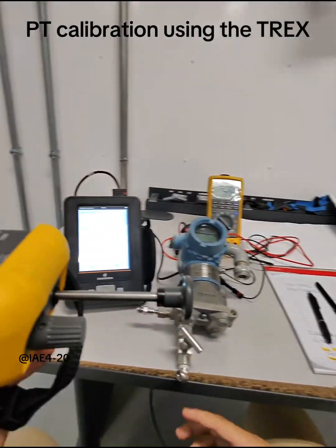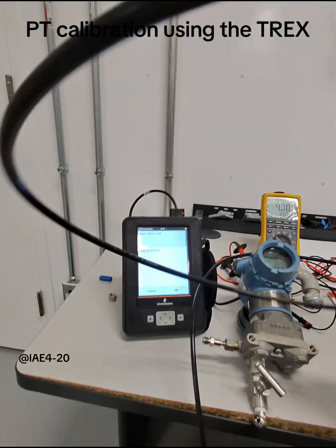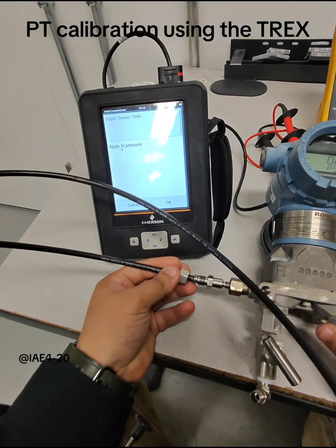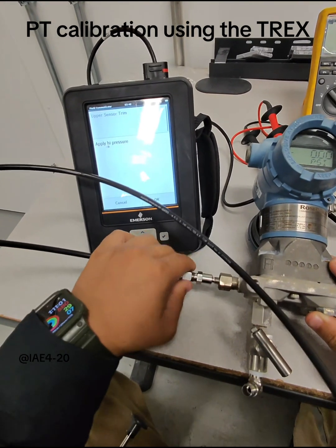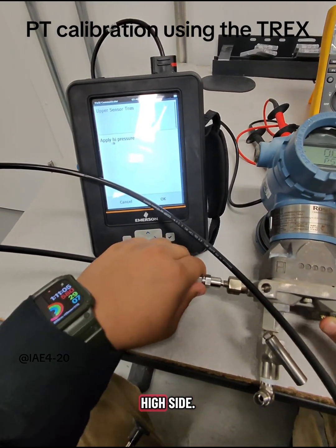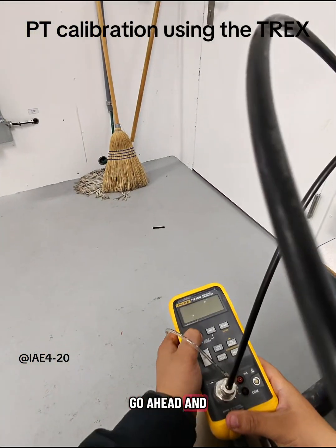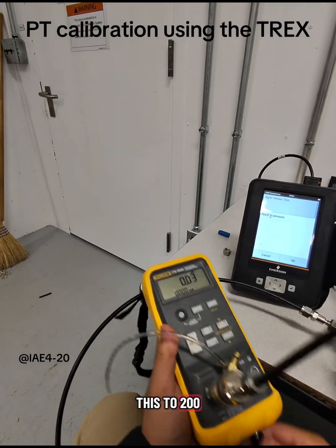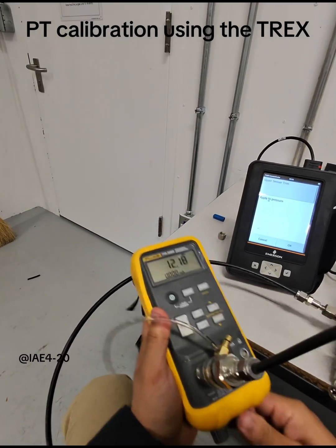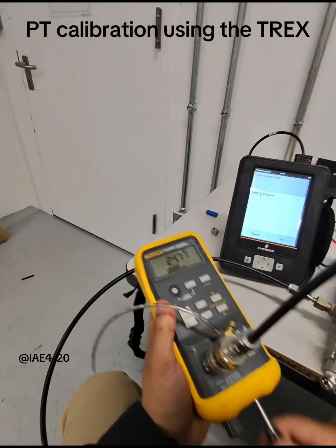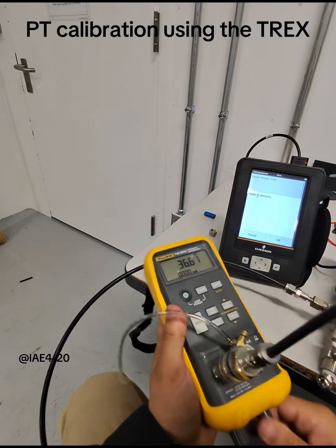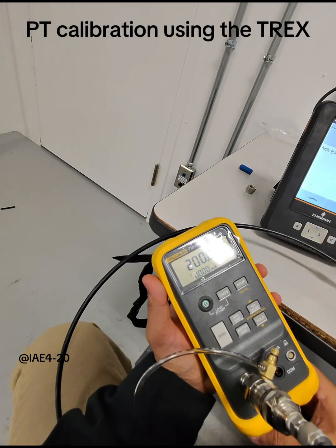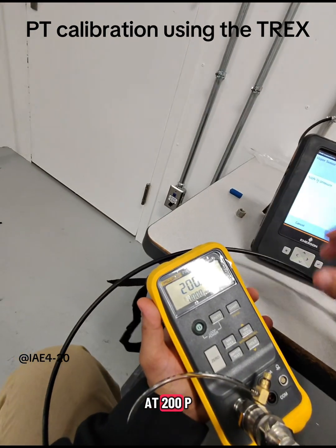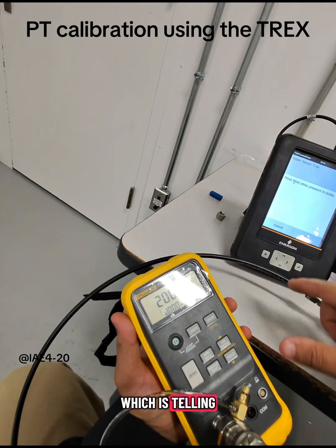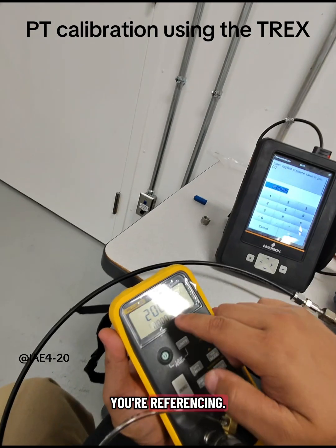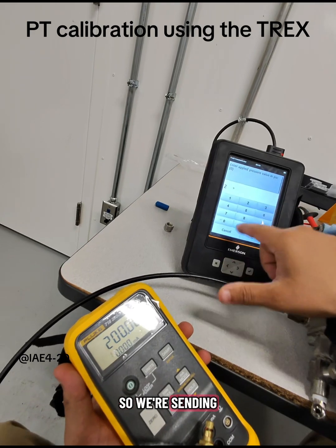We'll grab us a pressure pump. Remember, you always pump on the high side. Go ahead and turn it on. Alright, we're going to go ahead and take this to 200 psi. Alright, now that we got it at 200 psi, we're going to go ahead and hit OK, which is telling the transmitter that this is what you're referencing, 200 psi. So enter the applied pressure value. So we're sending it 200.